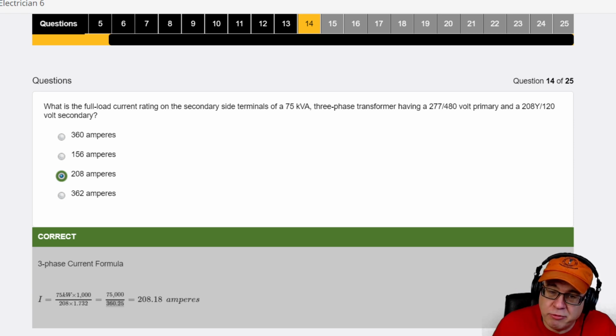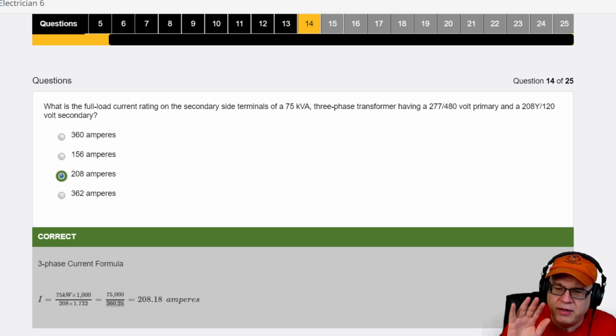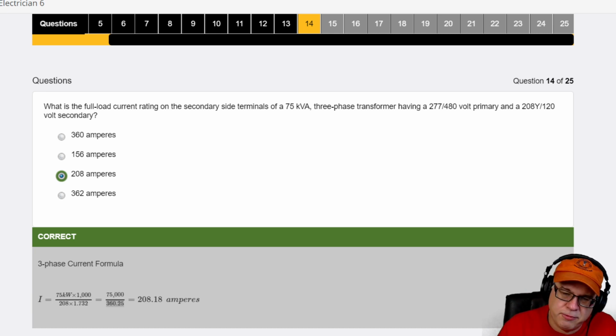To be honest, that's close to the extent most exams will go with transformers. It might also teach you 450.3 in the tables, primary protection at 250% and 125% secondary, or 125% primary, and no protection on the secondary if you only have primary protection. I cover all that in my transformer videos - it's a 6-part series. People ask me all the time to do something on transformers, but I already have an extensive series. I even teach secondary conductors, the 10-foot rule, the 25-foot rule, and all that in that series.